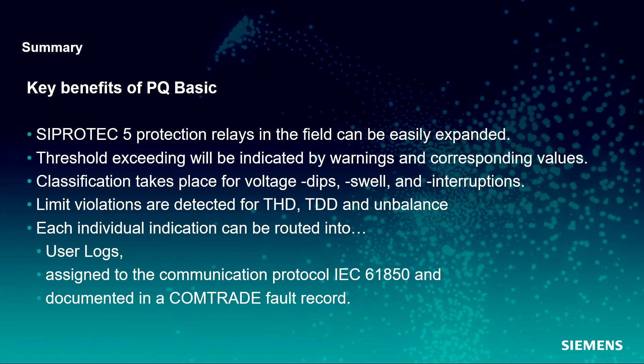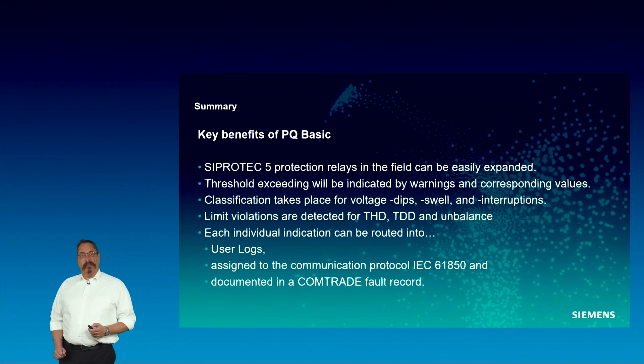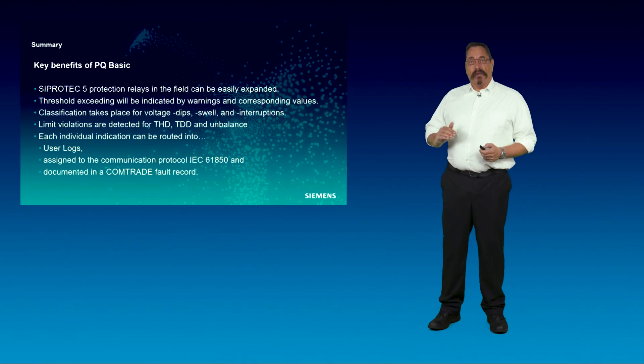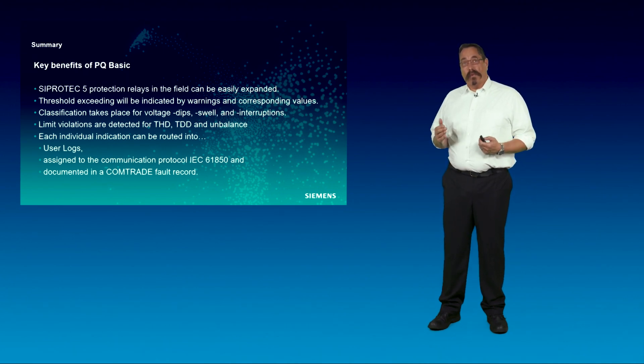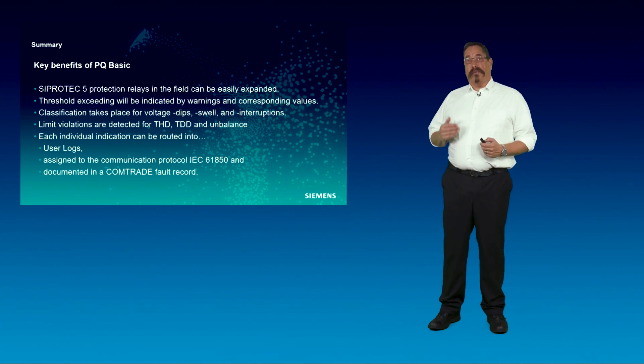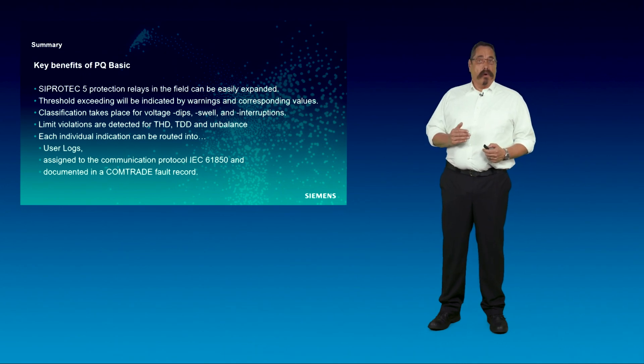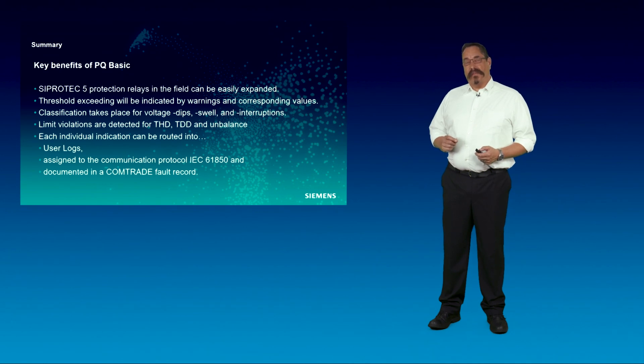Summary: already existing protection relays in the field can be easily equipped with power quality evaluation mechanisms without touching the hardware. Upper and lower limits — so-called thresholds — can be configured to customer needs. Evaluation takes place for events like voltage swells, voltage dips and voltage interruption, as well as total harmonic distortion, total demand distortion and unbalance. Warnings can be routed in the information routing matrix to user logs. The IEC 61850 protocol can transport warnings and extreme values forward to SCADA systems or via SICAM Q-S into the SICAM Q-Analyzer. A warning can initiate a complete record to provide a graphical interpretation of the event. That is the end of our presentation. Thank you for watching.